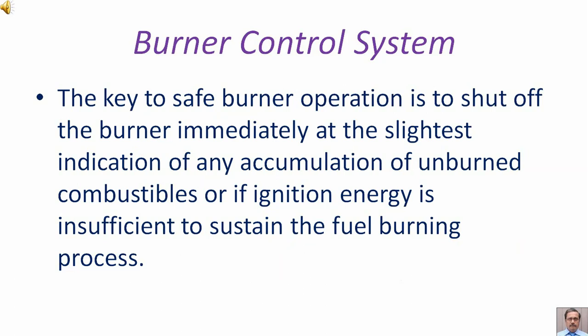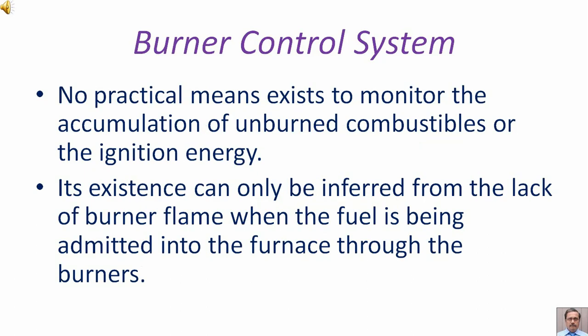The key to safe burner operation is to shut off the burner immediately at the slightest indication of any accumulation of unburned combustibles or if ignition energy is insufficient to sustain the fuel burning process. No practical means exist to monitor the accumulation of unburned combustibles or the ignition energy. Its existence can only be inferred from the lack of burner flame when the fuel is being admitted into the furnace through the burners.